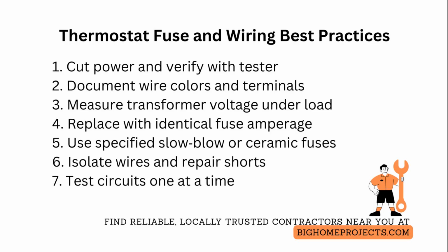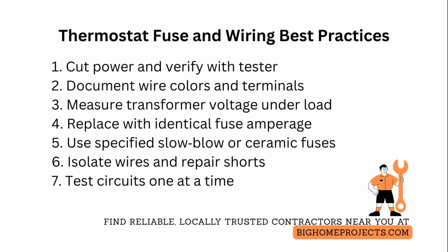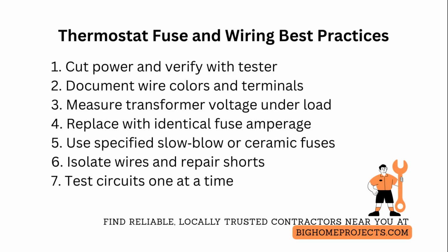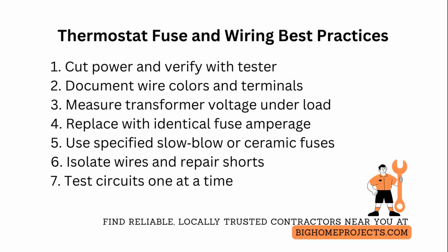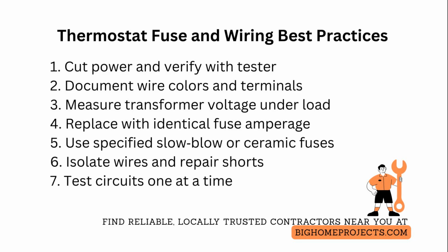Use slow blow fuses where the manufacturer specifies time delay behavior, and ceramic body fuses for high inrush protection when required. Match both amperage and fuse type. Before reapplying power, isolate the thermostat wires from the control board and measure continuity to detect shorts to ground or chafed insulation. Repair or replace any damaged wiring and use heat shrink tubing on splices.